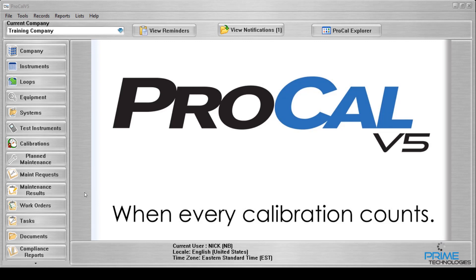Today I'll be showing you how to perform calibrations in ProCal V5. There are two main ways to perform calibrations within the software. One is to perform a manual calibration and the other is to use the field calibrator utility to download a tag to a calibrator such as the Fluke 754, perform your work on that calibrator, and then upload that calibration back into the software.